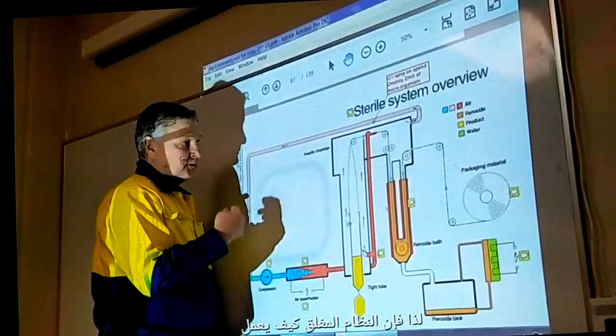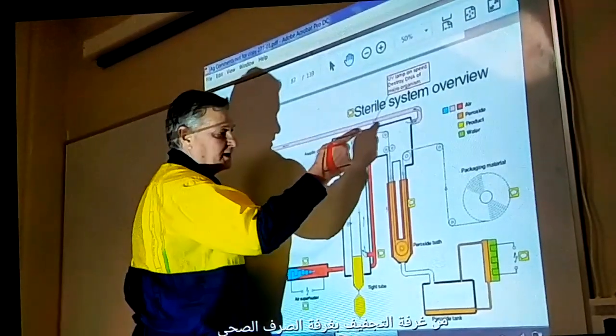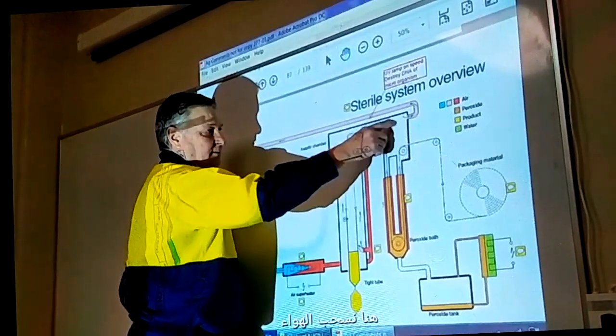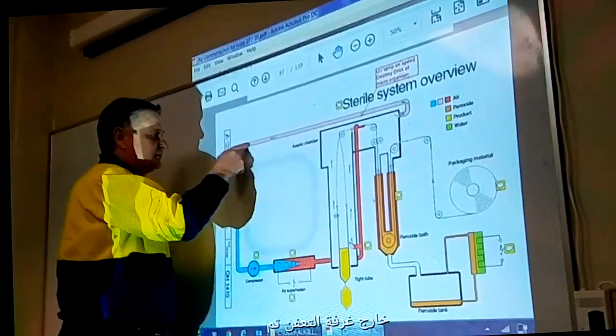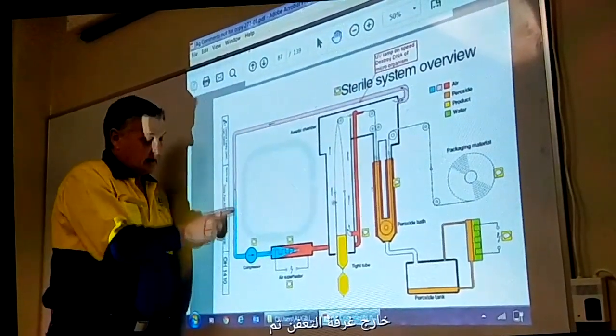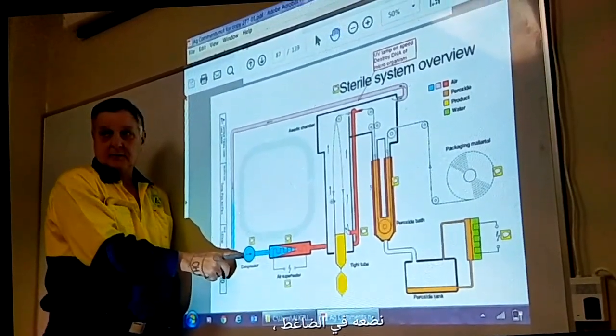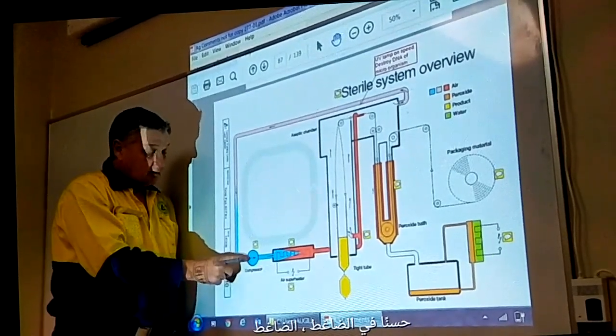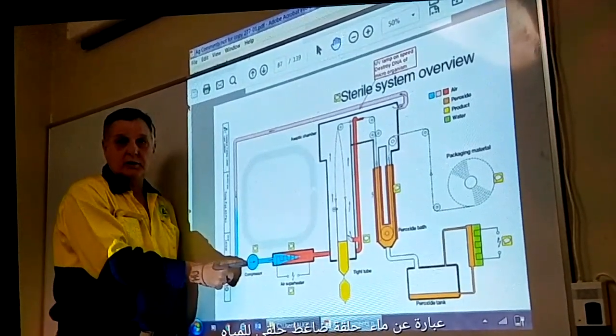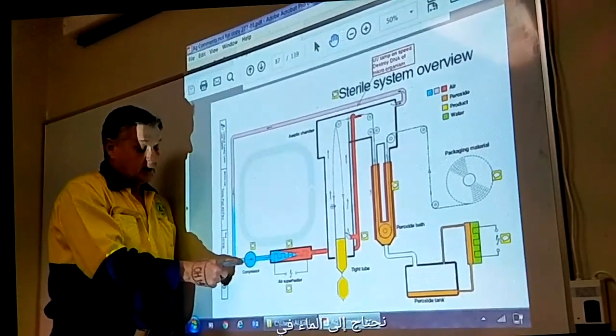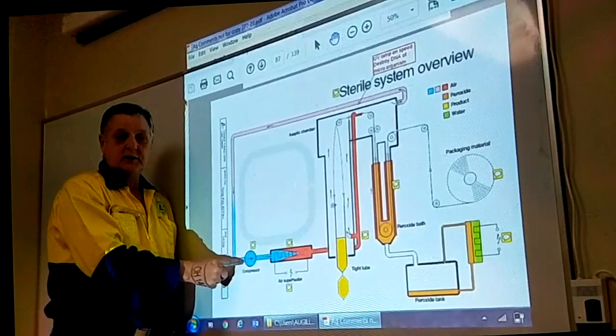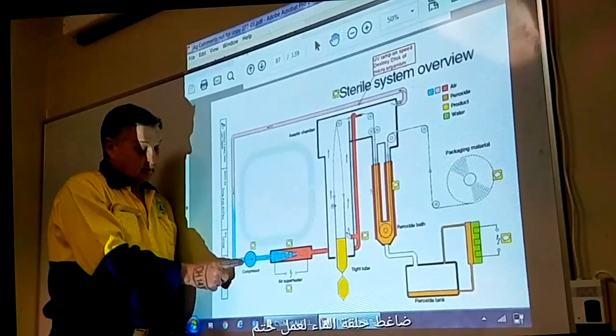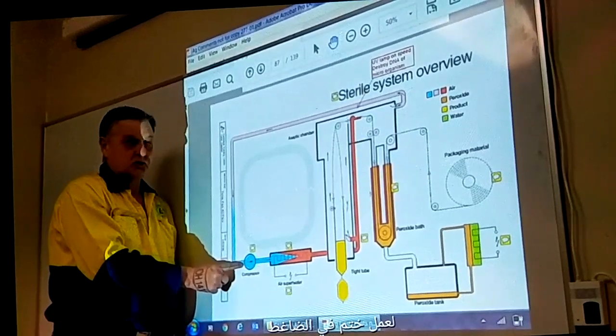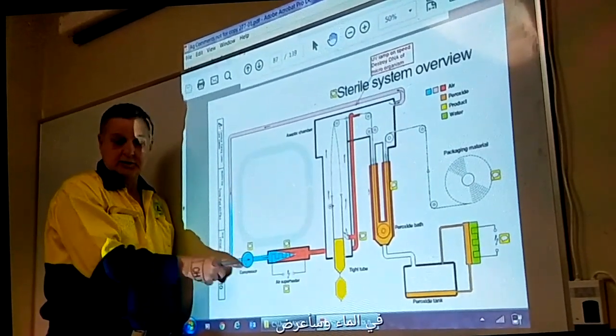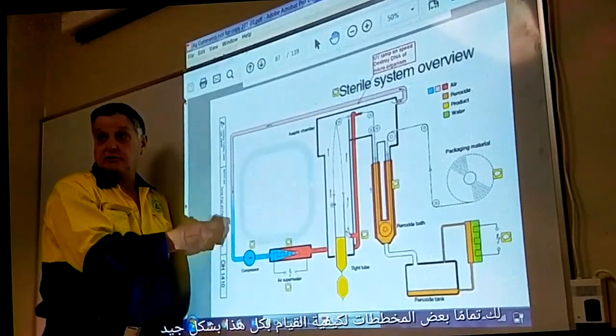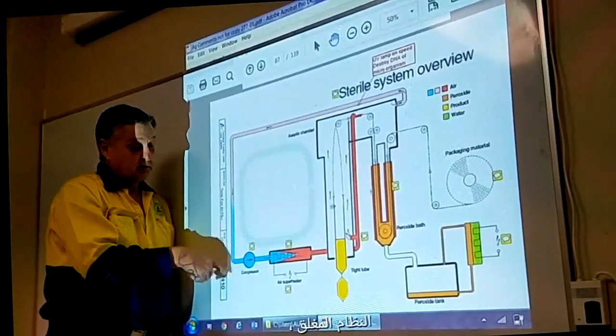So, the closed system, how does it work? From the aseptic chamber, drying chamber, here, we drag air out of the aseptic chamber. Then we bring it down into a compressor. Okay? Into a compressor. The compressor is a water ring compressor. We need water in the water ring compressor to make a seal, to create a pressure in the water ring compressor. I'll show you some diagrams of how we do all this, okay? But this is just a basic overview of the closed system.